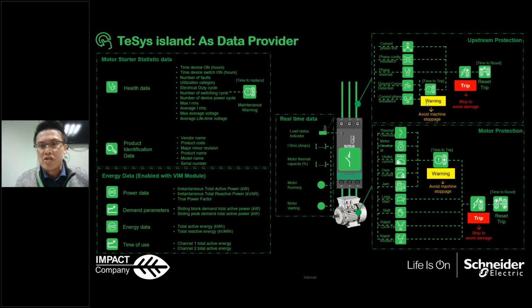For the upstream protection, we still need circuit breakers to protect the system. But as I said, because the overload protection is already built into the TeSys island, what you need to consider is only the short circuit protection for the circuit breakers. You do not need to consider the thermomagnetic one. You only need to consider the magnetic one for short circuit protection. And for this upstream protection, you can have current phase loss, current mismatch, phase mismatch, phase reverse. So all these upstream protection data you can also have inside the bus coupler.